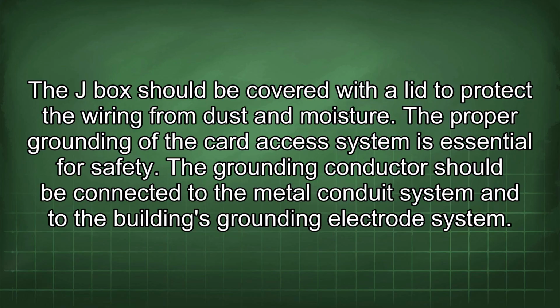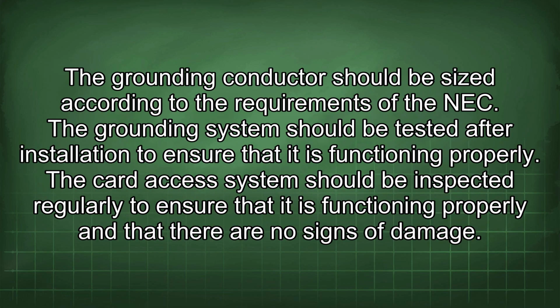Proper grounding of the card access system is essential for safety. The grounding conductor should be connected to the metal conduit system and to the building's grounding electrode system. The grounding conductor should be sized according to the requirements of the NEC. The grounding system should be tested after installation to ensure that it is functioning properly.